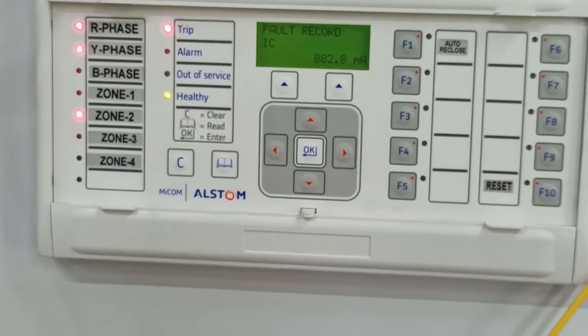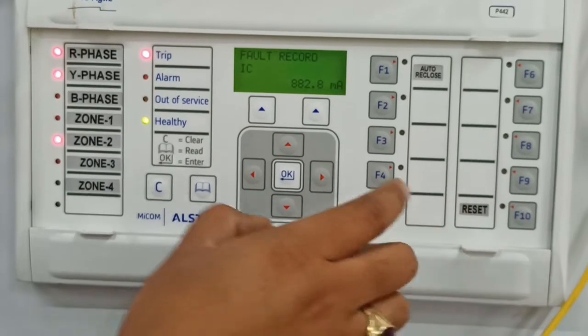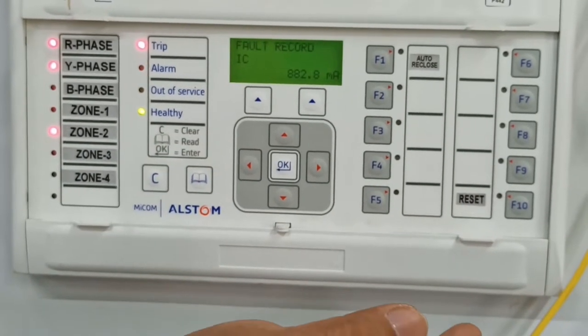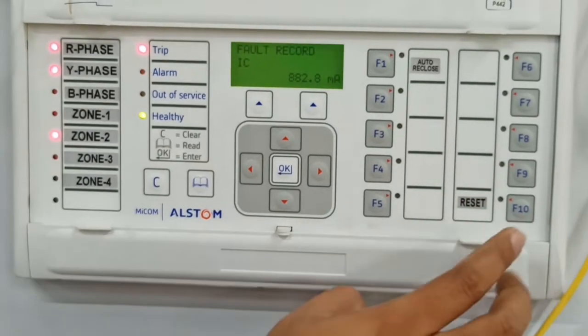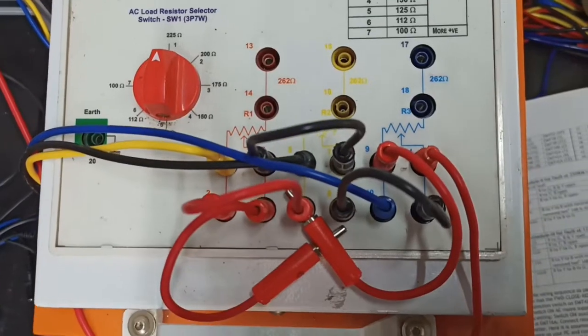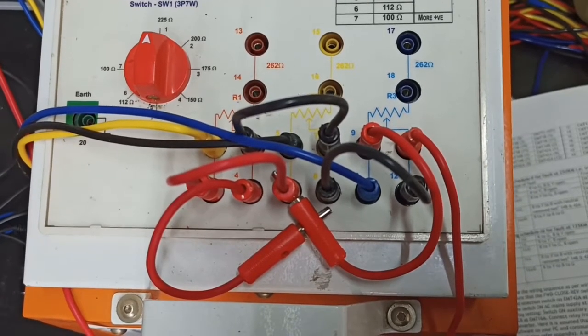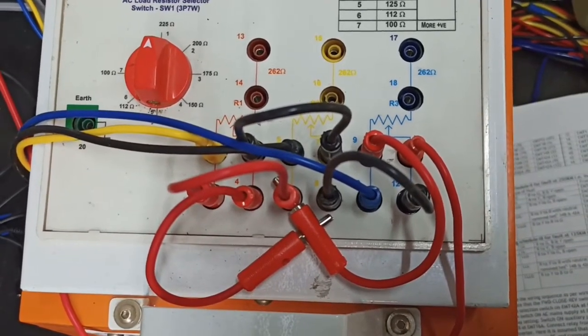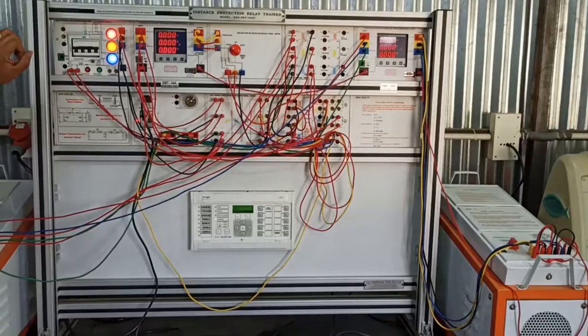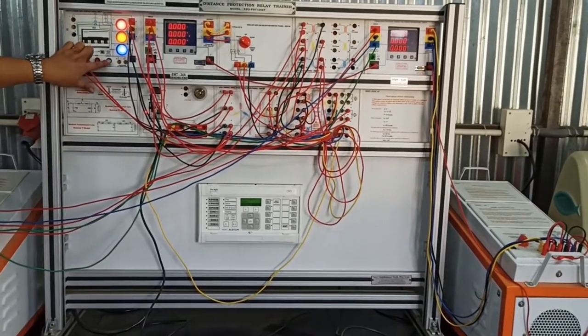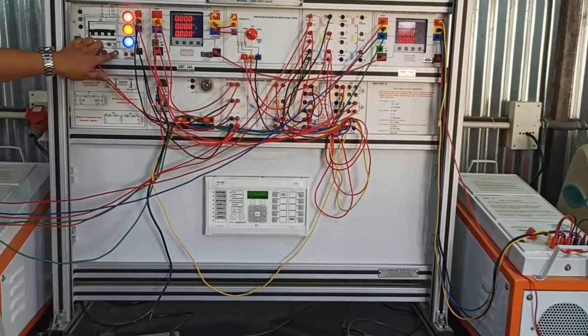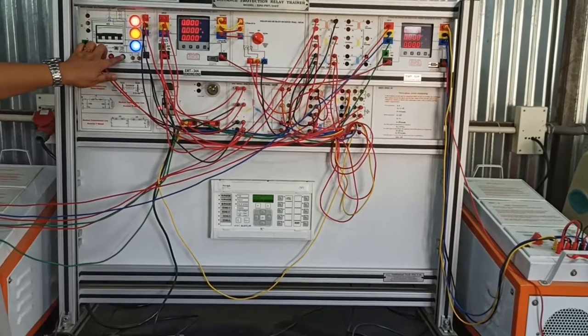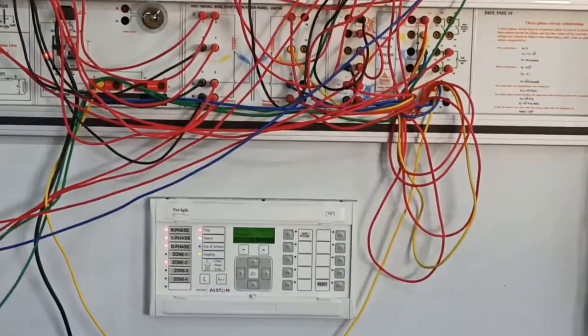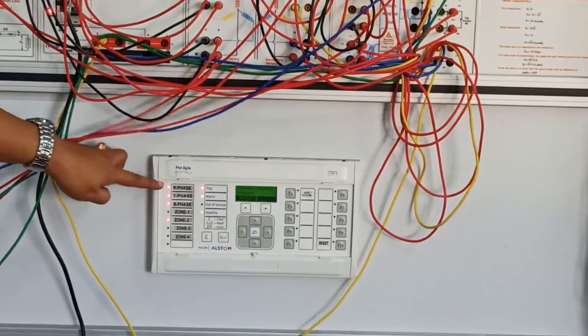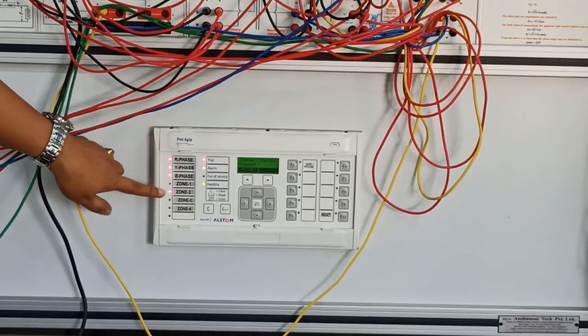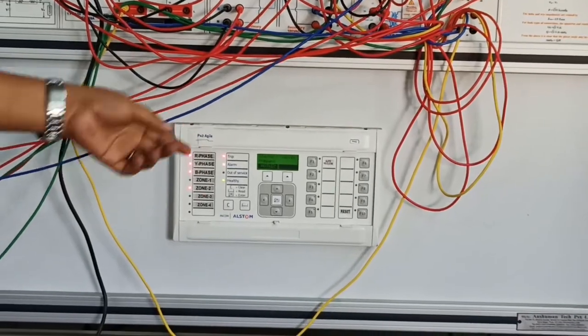Now we will again reset it and make a three-phase to ground fault, and see what reading comes out. Now we have made the connection for the three line to ground fault, that is triple LG. Then we have to press the start button, and the fault will be detected by the relay. Now the fault is detected by the relay, and it is in zone 2. Let's see the reading in the display.